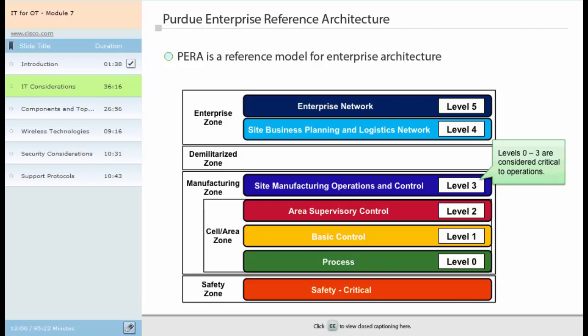In Level 4, the Site Business Planning and Logistics Network is where functions and systems exist that require access to services provided by the enterprise network. A manufacturing zone comprises Levels 0 to 2 incorporated into the cell area zone, as well as Level 3. Level 3, the Site Manufacturing Operations and Control Systems, manage plant manufacturing-wide functions. These systems may communicate with controllers in Level 1, function as a staging area for changes in the cell area zone, and share data with the enterprise systems in Levels 4 and 5. Because these systems are primarily based on standard computing equipment and operating systems, they are more likely to communicate with standard networking protocols.